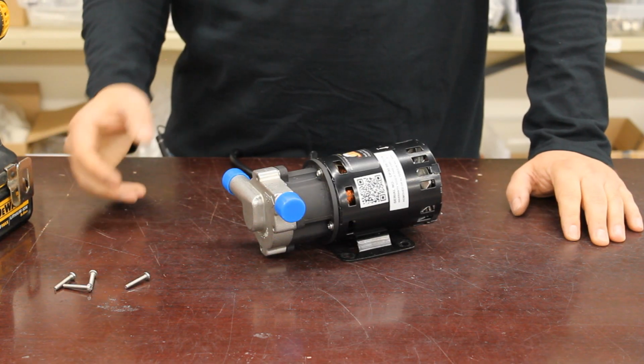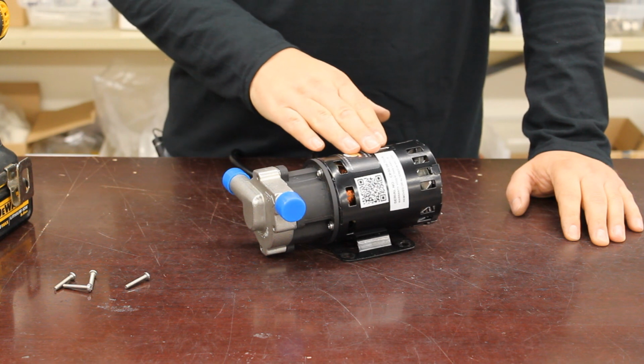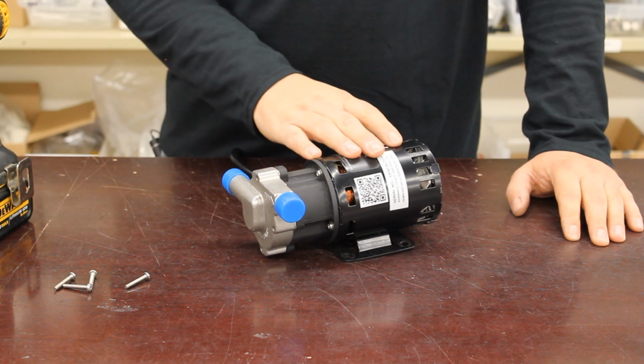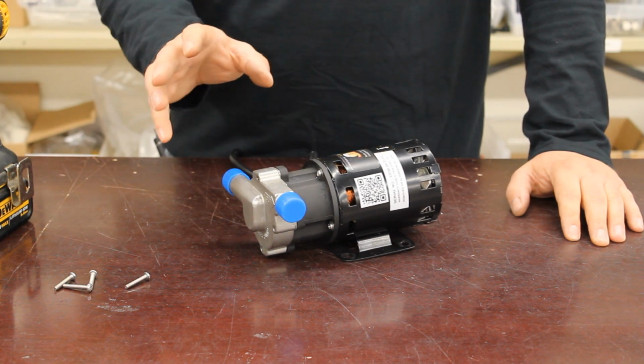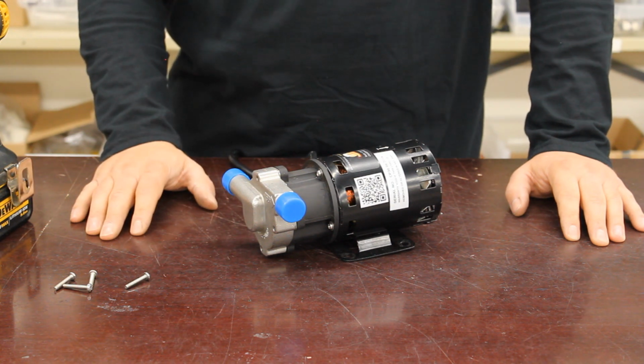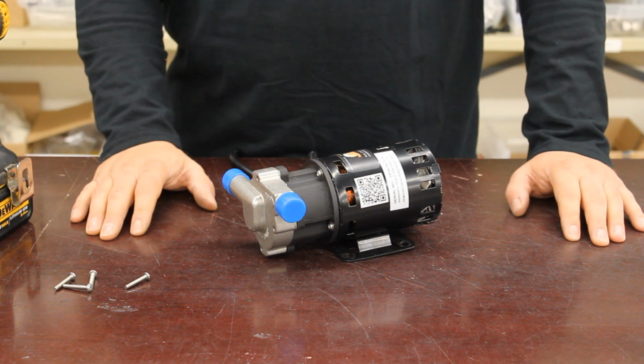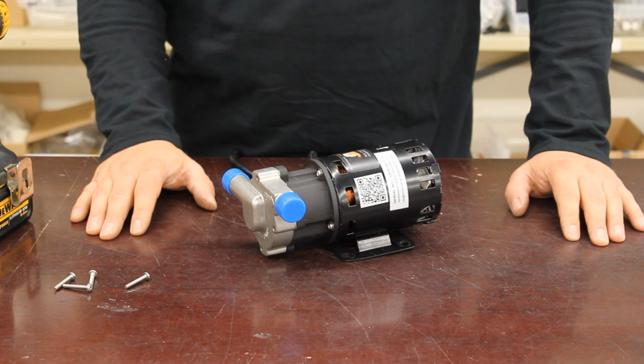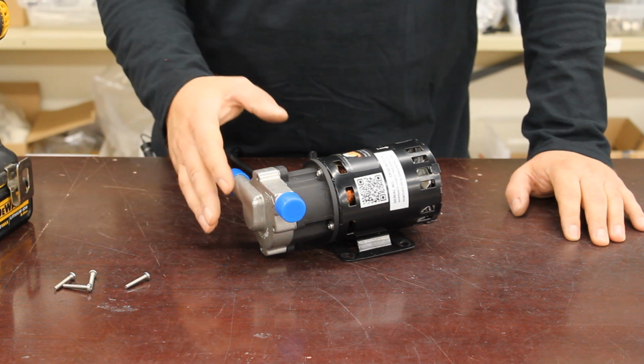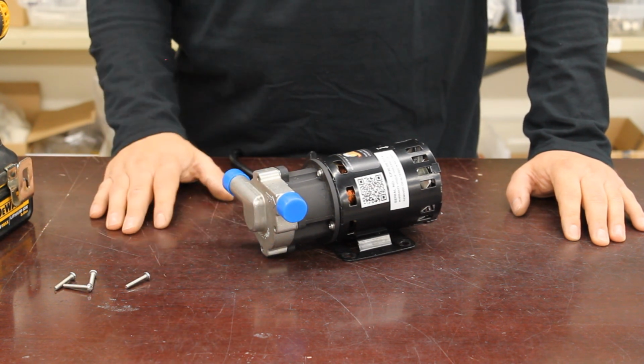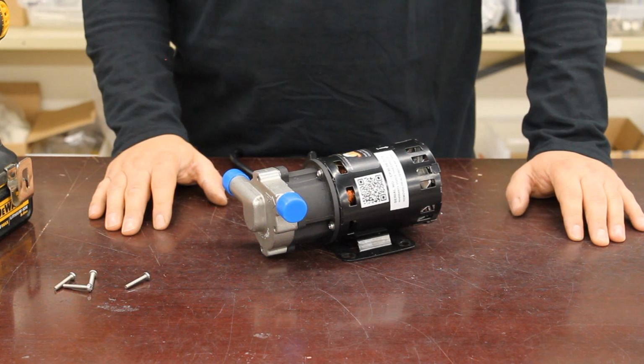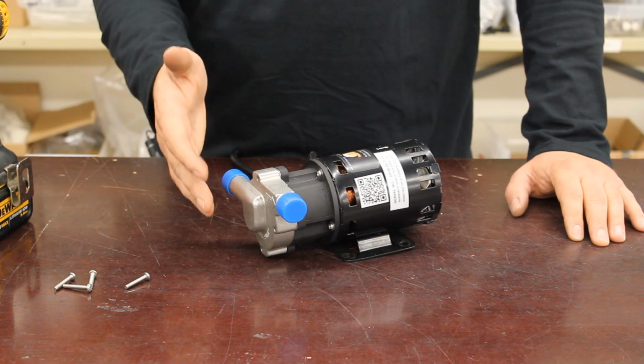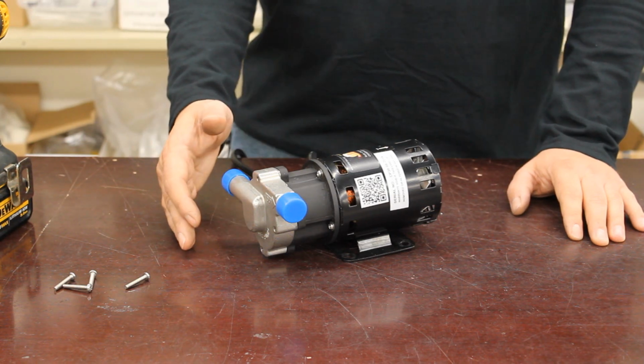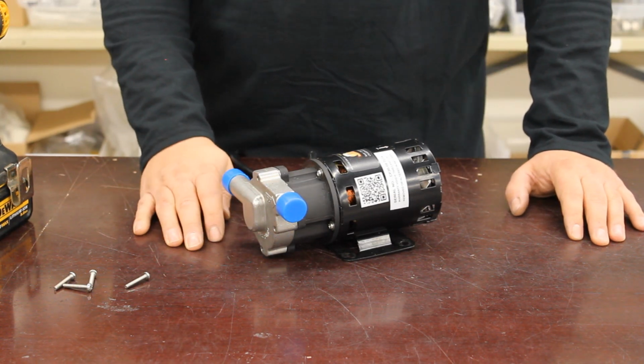Troubleshooting condition number 2 is when you plug the motor in, the motor spins fine, there's no trouble there, but you cannot pump any liquid, or the liquid does not pump. The first condition that might be causing that problem is that you haven't fully primed the pump. Now, this may be the case for new pump owners who are just not as familiar or practiced with getting the pump primed. And so let's go over those steps real quick.